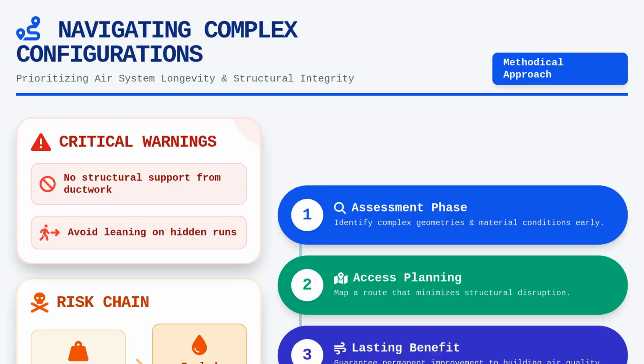Navigating complex configurations requires a methodical approach that prioritizes the longevity of the air system. Tight hidden runs often force technicians into difficult physical positions, but you must avoid using the ductwork itself as a structural support for yourself or your equipment. Heavy accessories or poorly supported branches can cause sagging, which leads to pooled debris and standing water in low points.